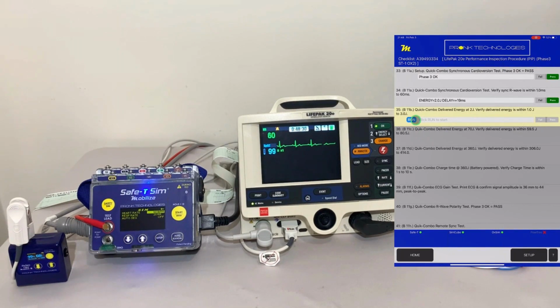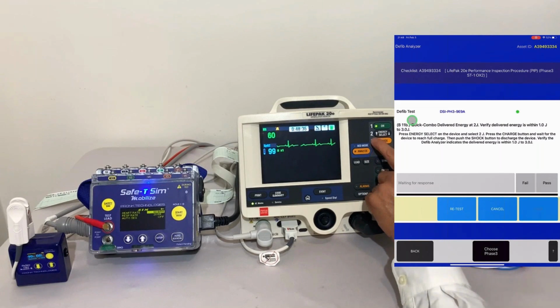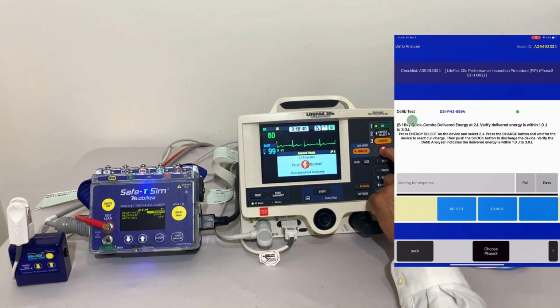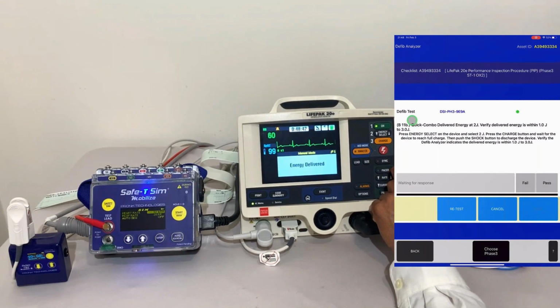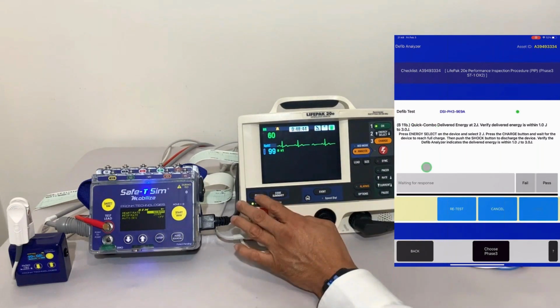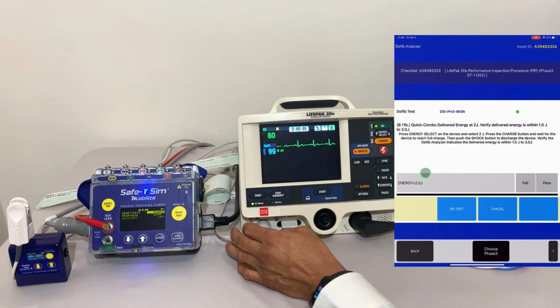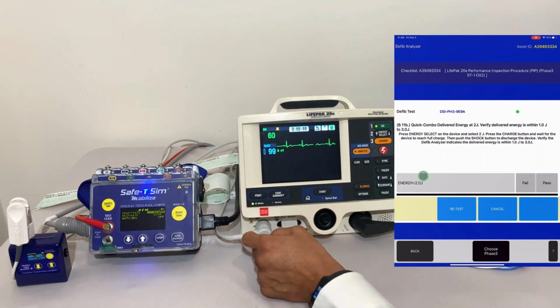The next test is we're going to do some discharge tests now, where we're going to verify the discharge values are within range. First test is 2 joules. We're going to run that. Again, charge up the defibrillator to 2 joules, which we set it for in the prior test. We're going to charge it. We're going to fire. And we're going to make sure that the result coming back from the defib analyzer is 2 joules, and it's exactly right on the mark. So we're going to go ahead and confirm that test as a pass.